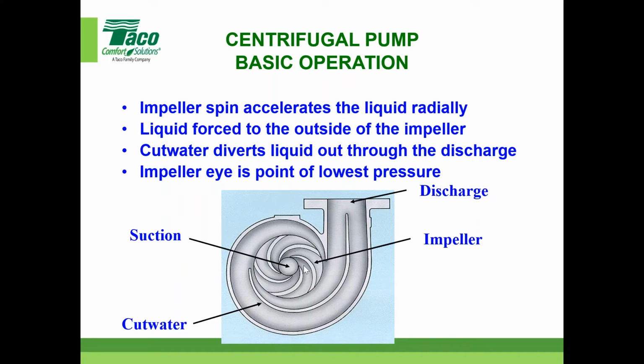And I think the opposite is true. If the system is not well maintained, the fluid is not cleaned properly, dirt and air not removed, the impeller can be impacted. We can also have cases with net positive suction head or cavitation issues—sometimes you have cavitation because you don't have the proper pressure on the inlet side of the pump, and you can't hear it. It might be very slight, but that will tend to deteriorate the impeller over time.